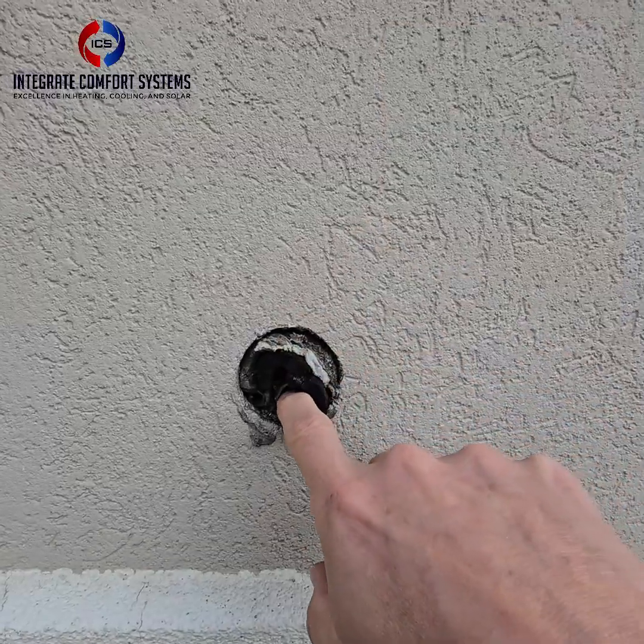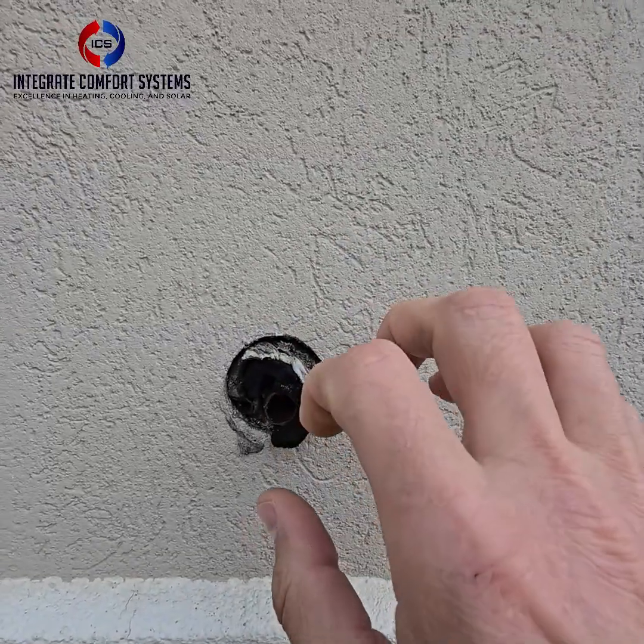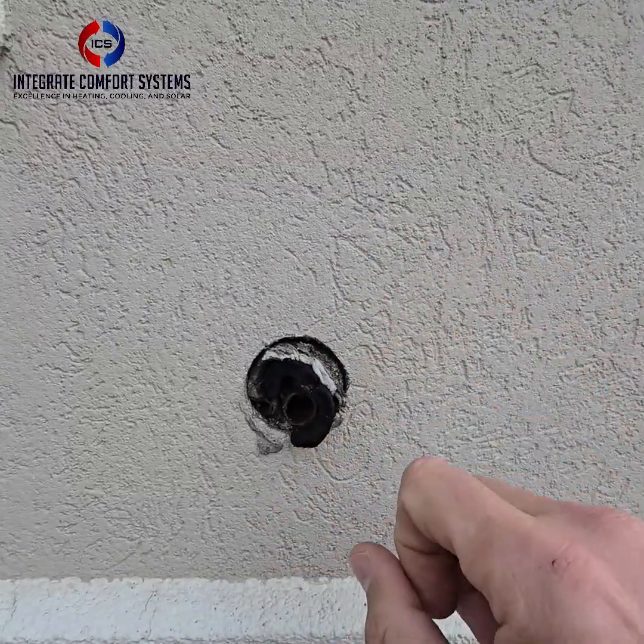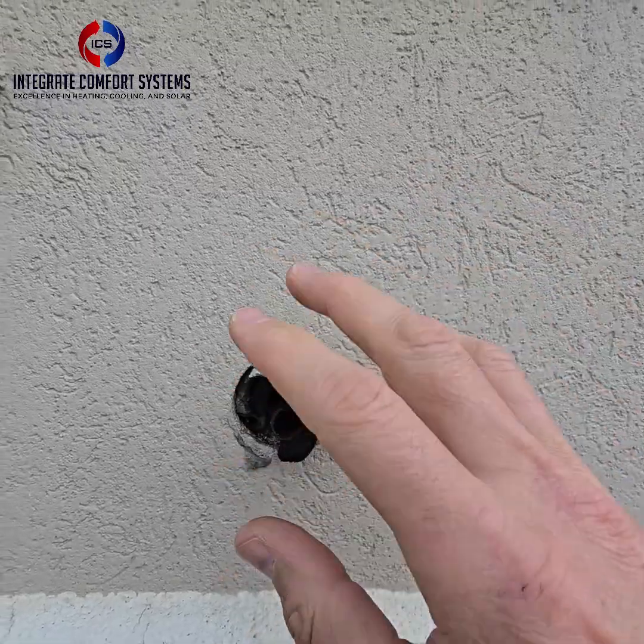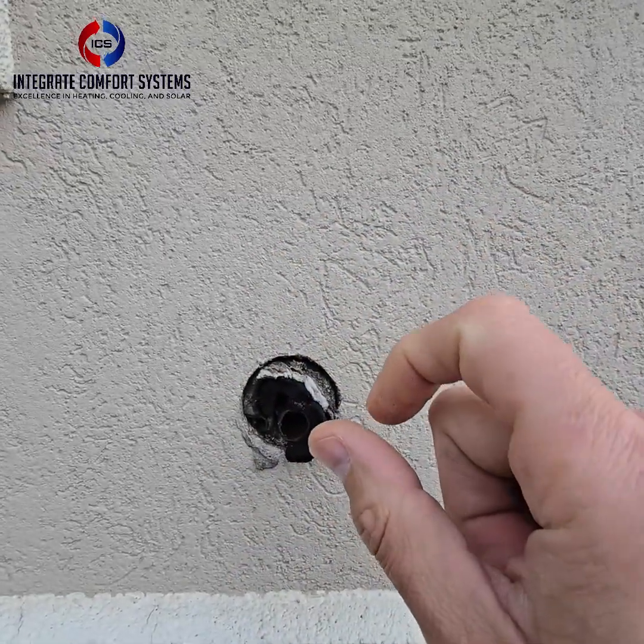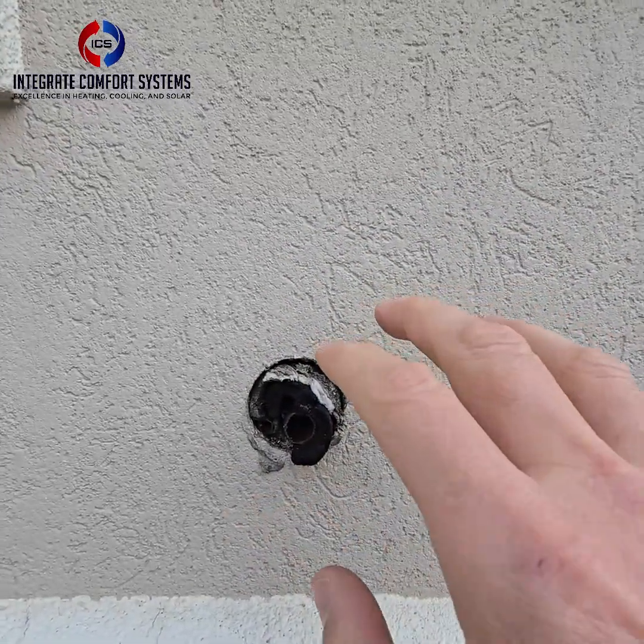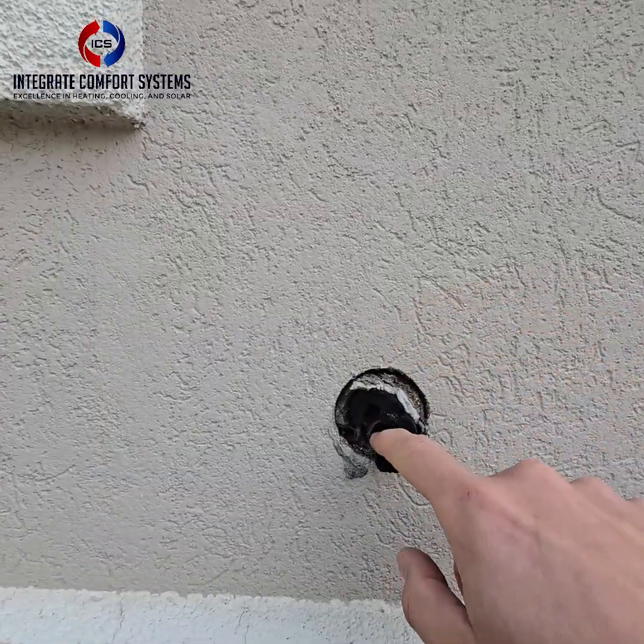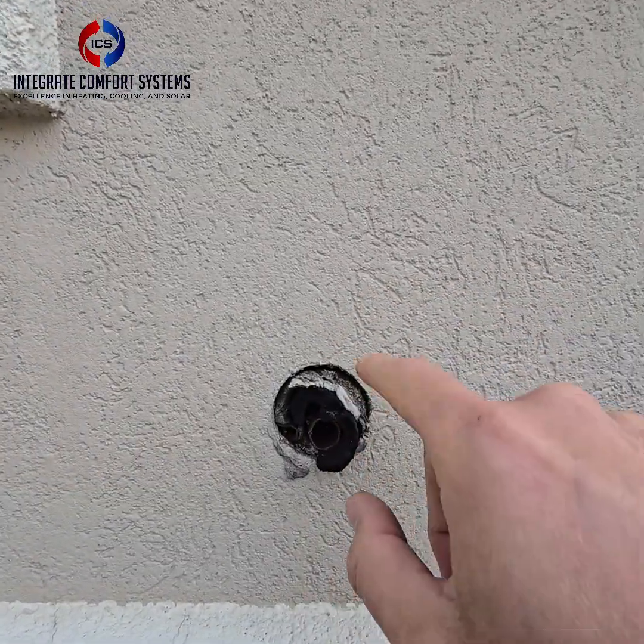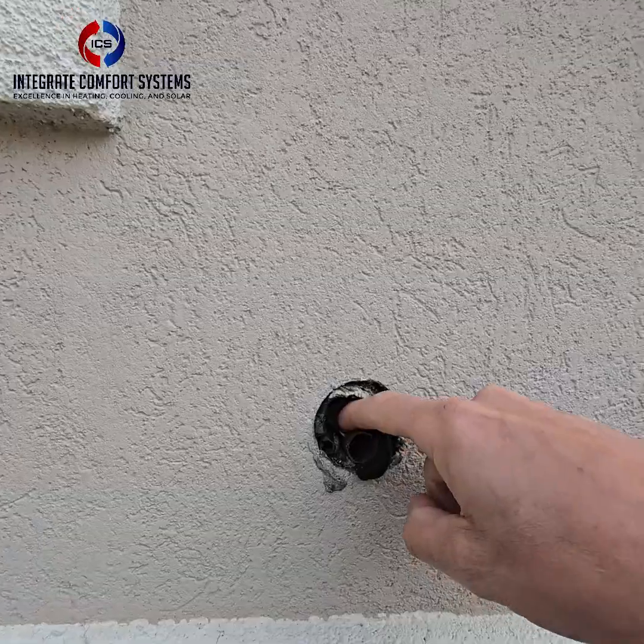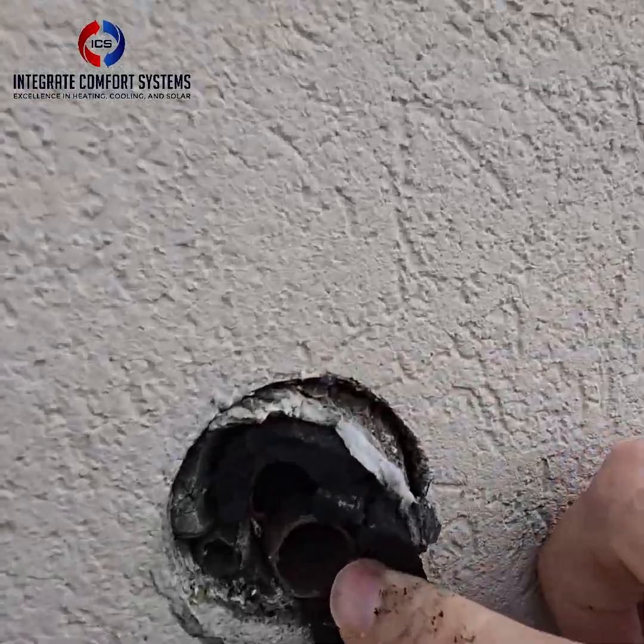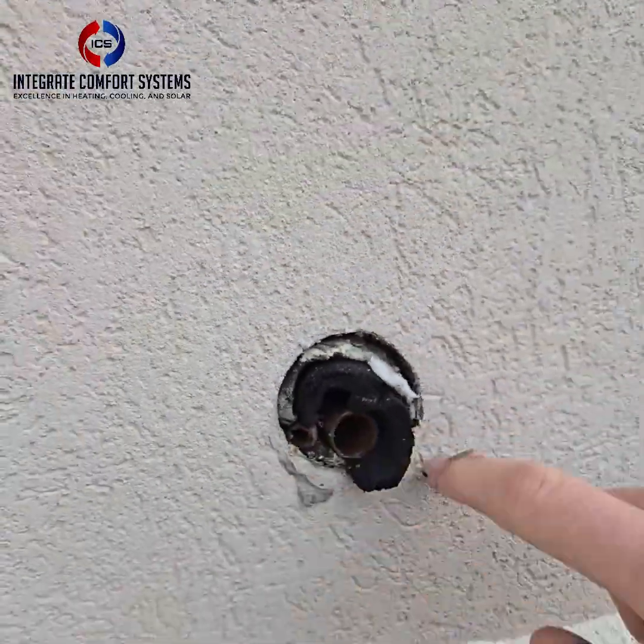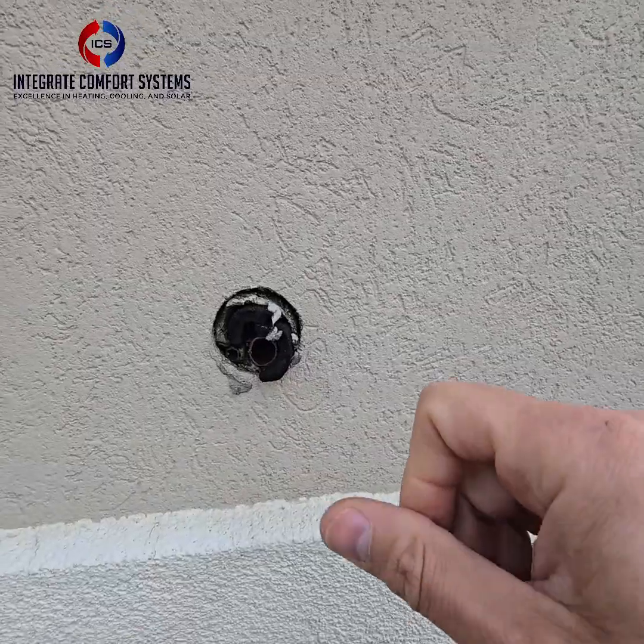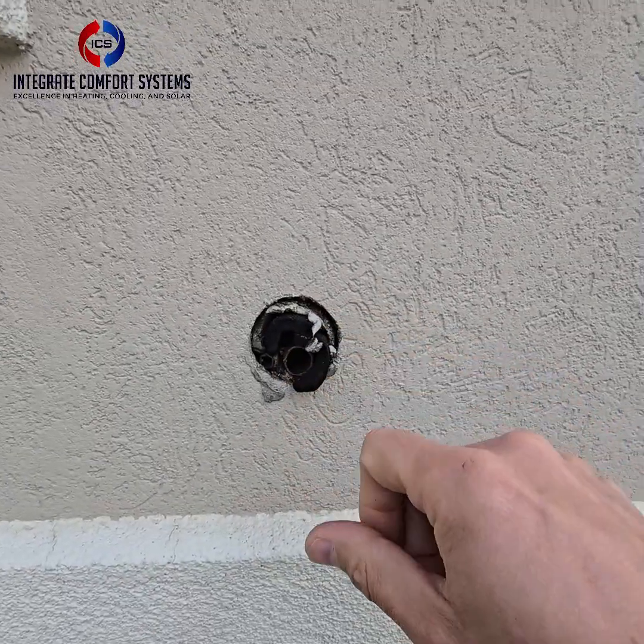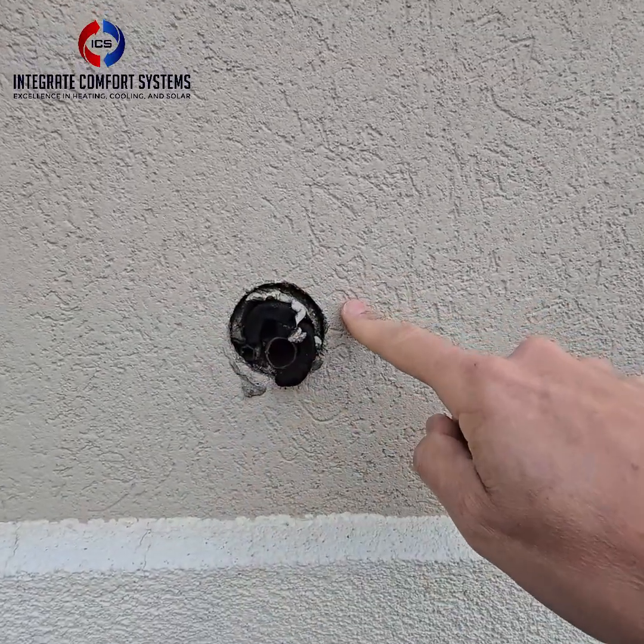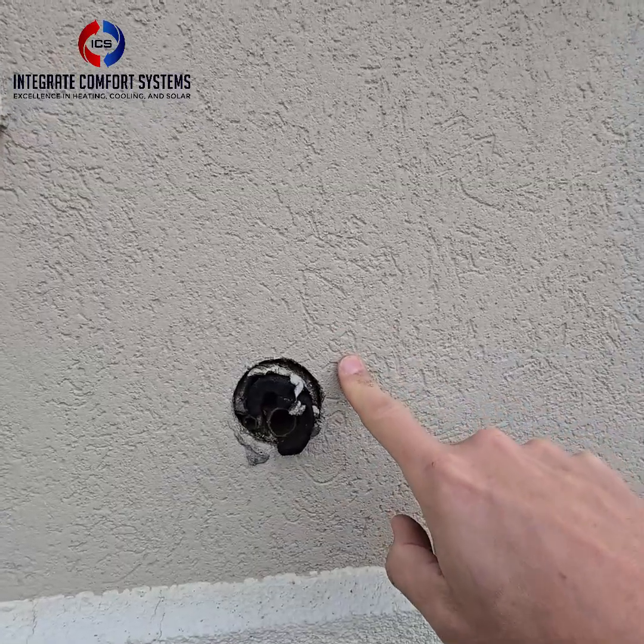And these pipes, believe it or not, they're not just stationary, they move. As the AC unit turns on, turns off, whether it's a heat pump or AC only, you're going to get expansion and contraction of copper, and you're going to get slight movement against the surfaces. And what happens is that it keeps rubbing and rubbing and rubbing, and over time we find a lot of leaks right there at this penetration point, on top of eating away at the structure, on top of being an entry point for bugs, but also especially against concrete.